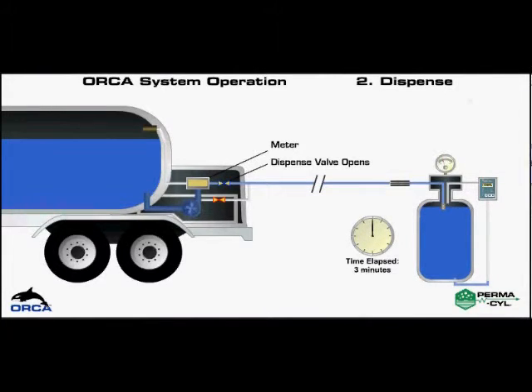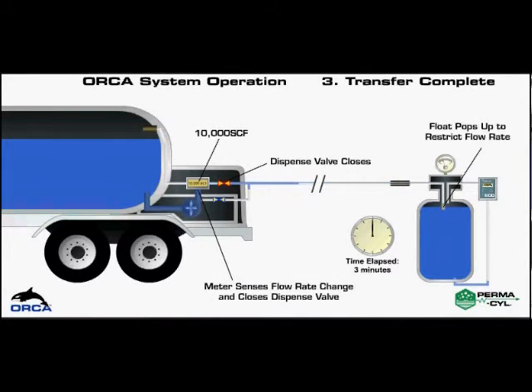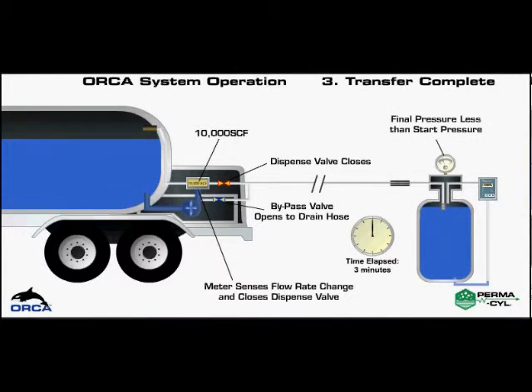This quick 3 minute delivery is terminated automatically when the Perma-Cyl top fill float assembly lifts. At the end of the delivery, the control system terminates the delivery by closing the dispense valve and the remaining product in the hose automatically drains back into the Orca. It is now safe to disconnect the hose from the Perma-Cyl. Stow the hose and close the cabinet doors before moving on to the next delivery location.